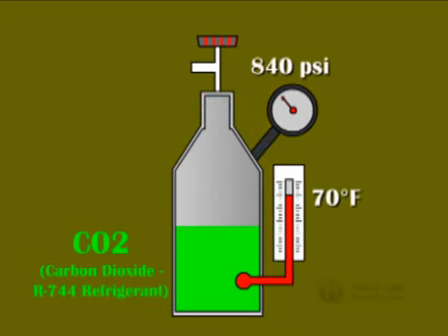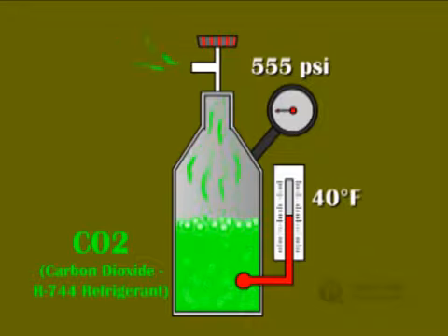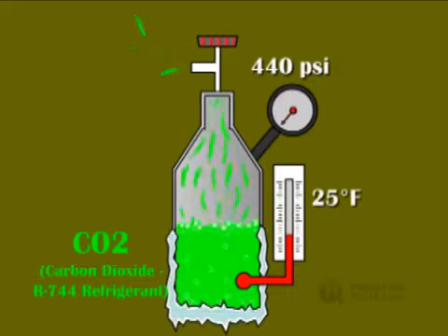When a refrigerant evaporates, or boils, it absorbs heat at a very high rate, as is the case with all liquefied gases. Since refrigerant has a lower boiling point than most liquids, we can easily manipulate it so that the only heat source needed is room temperature air. We can control this boiling point by altering the pressure placed upon the liquid.